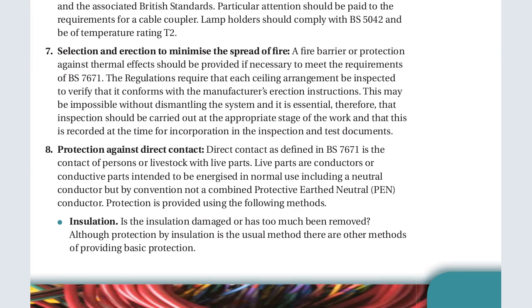Another one is the protection against direct contact. We can provide protection against direct contact by insulation. We have to make sure that the insulation is okay, and also the earthing. Direct contact is defined by BS 7671 as the contact of persons or livestock with live parts. The live parts are conductors or conductive parts intended to be energized in normal use, including the neutral conductor but, by convention, not a combined protective earth and neutral conductor, that is the PEN conductor.